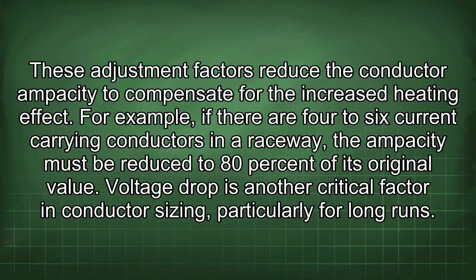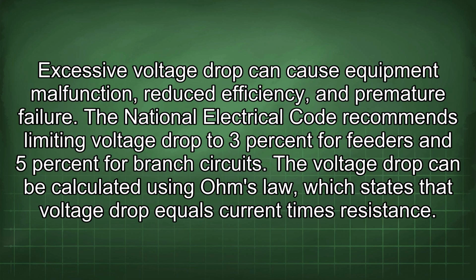For example, if there are 4 to 6 current carrying conductors in a raceway, the ampacity must be reduced to 80% of its original value. Voltage drop is another critical factor in conductor sizing, particularly for long runs. Excessive voltage drop can cause equipment malfunction, reduced efficiency, and premature failure. The National Electrical Code recommends limiting voltage drop to 3% for feeders and 5% for branch circuits.